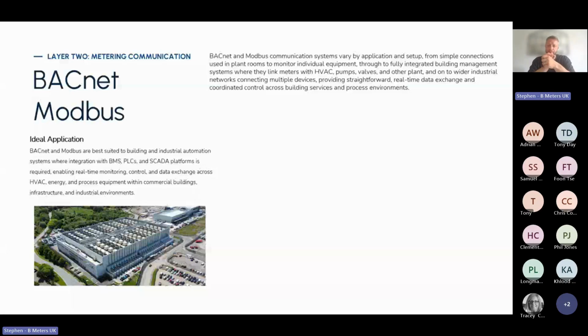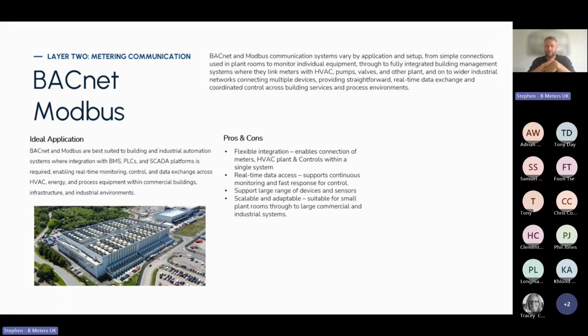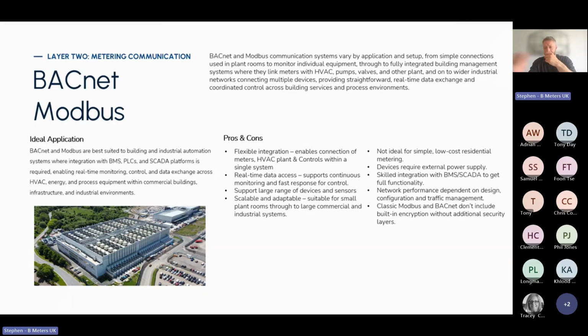Pros and cons. Pros, again, very straightforward: flexible integration, real-time data access, supports a large range of device sensors, scalable and adaptable. On the other side, not ideal for simple low-cost residential metering for sure. With BACnet and Modbus, you don't get it on mechanical meters. The devices require an external power supply. BACnet not so much, but Modbus you will see on electricity meters, ultrasonic meters, and mag flow meters, but the standard classical mechanical water meter is definitely not.